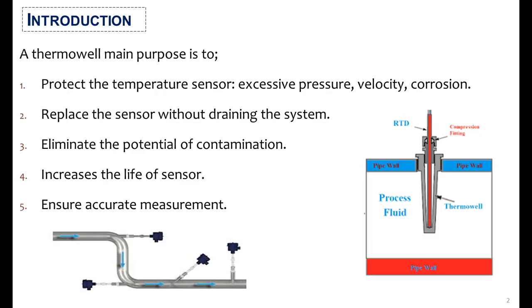The main purpose of a Thermowell is to protect the temperature sensor from excessive pressure, velocity, corrosion, and erosion. It also helps to replace the sensor without draining the system, eliminates the potential of contamination, and increases the life of a sensor. Hence, it ensures accurate measurement.